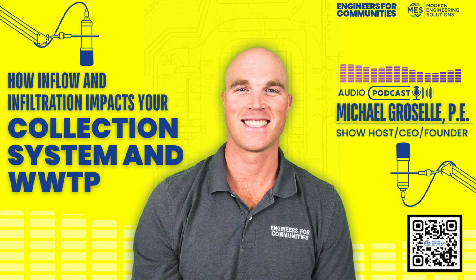Another thing to think about is manhole inspections. So someone can visually open up a manhole, pull the lid off, and look in, and see if there's water coming in from the cracks and such. So things to look at: Do you have cracks around the cover? Do we need to potentially replace that or put some sort of sealant in? Is there water coming from cracks in the side of the concrete or at those joints? Did they put that joint sealer in there? So you could do visual inspections and find direct problems in there.